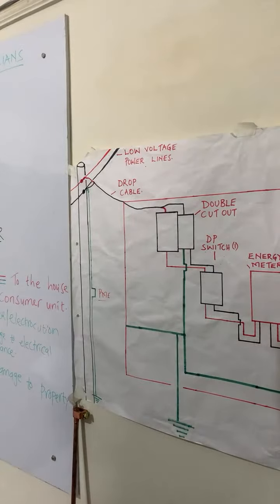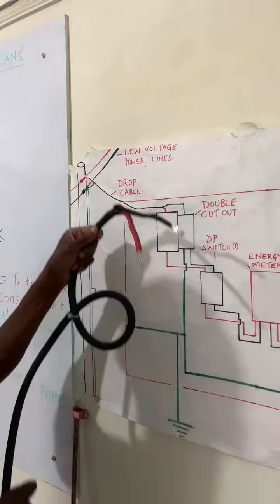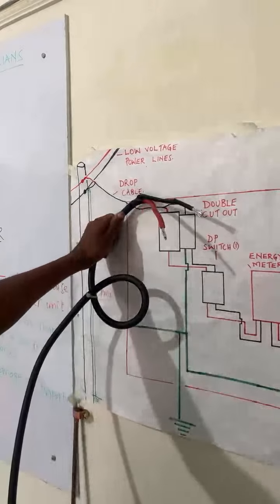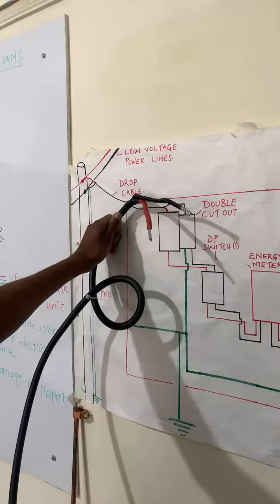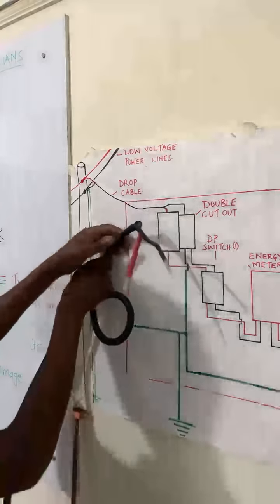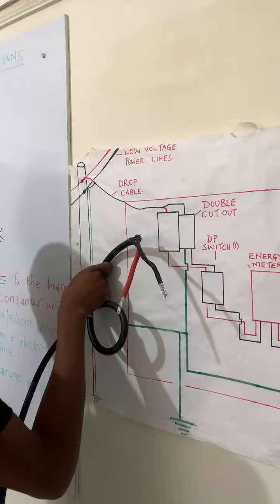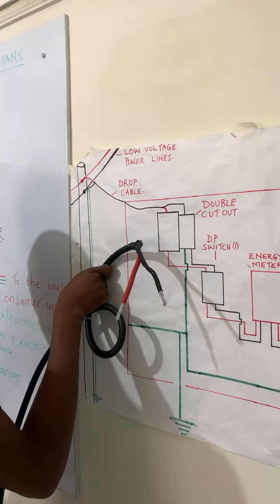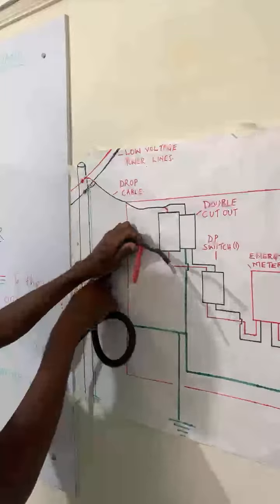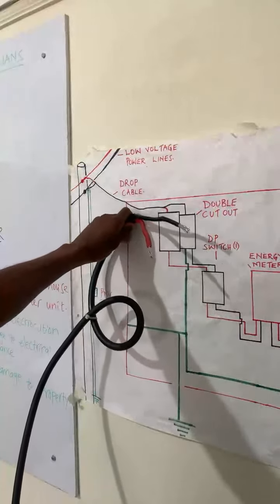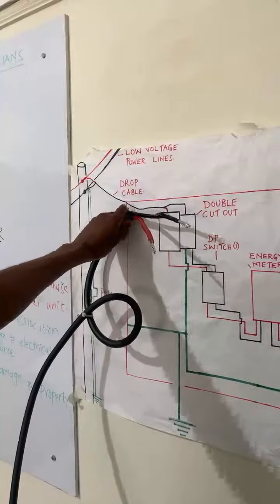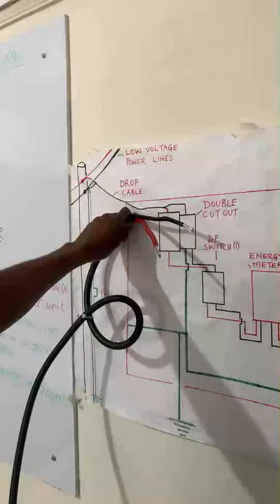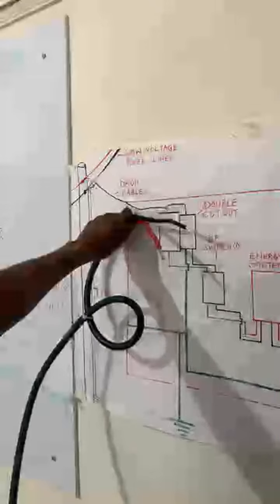The drop cable comes with only two connections, like so. So we have the neutral and the phase, or we have the phase and the neutral, whichever comes first. But normally it is the phase and then the neutral, because the neutral will act as a return path. So the red cable is representing the phase, and this black here is representing the neutral.